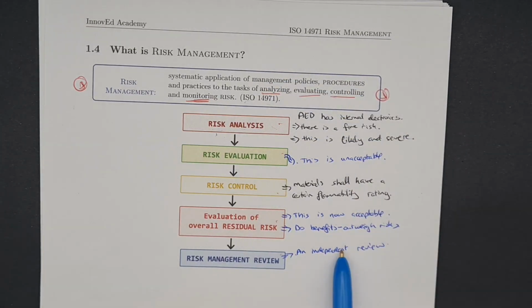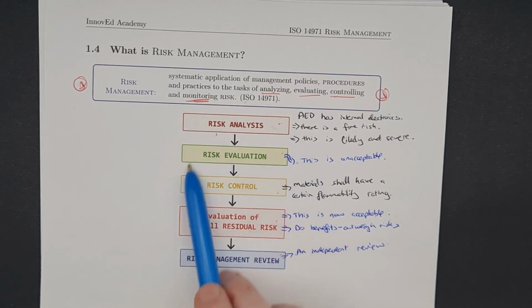It might also be helpful to bring in a person with a clinical background who understands the clinical and use risks better than engineers, but you do want a mixture because risk management is very interdisciplinary. You're going to want an electronic engineer to talk you through the flammability stuff and anything related to IEC 60601, and for any software related risks, you're going to want a software developer, etc. So that's the independent review. You want them to not have worked on risk management, but be subject matter experts.